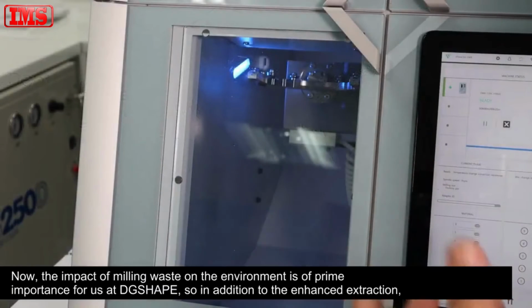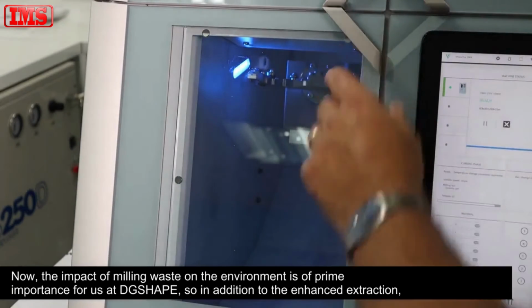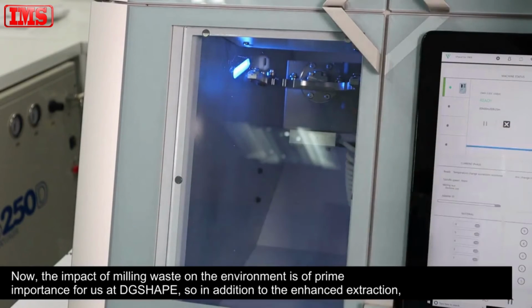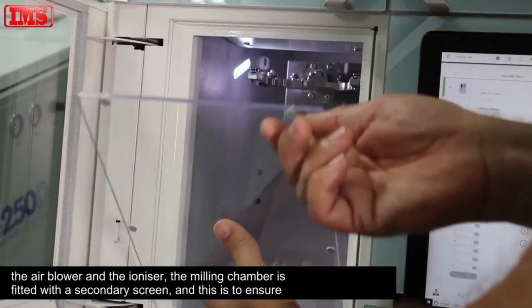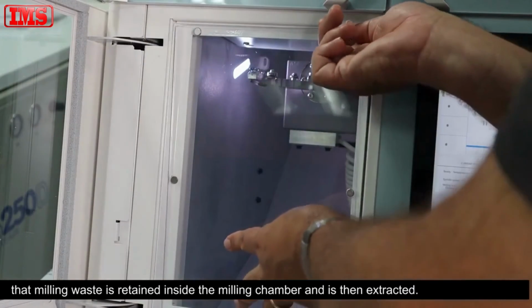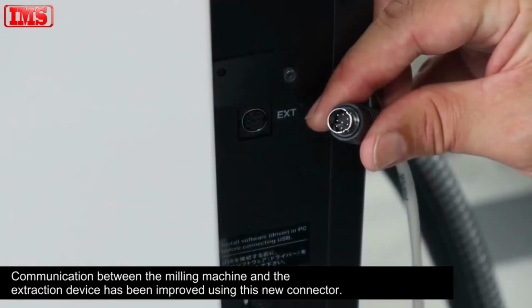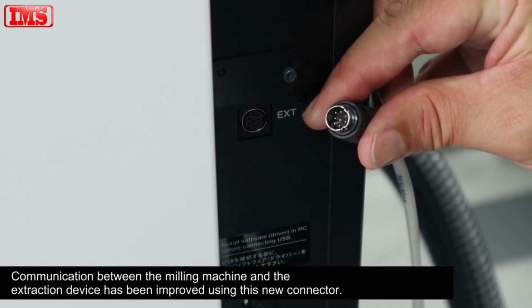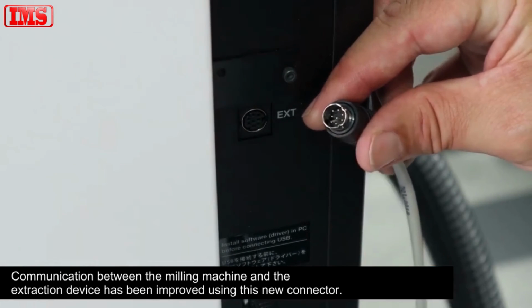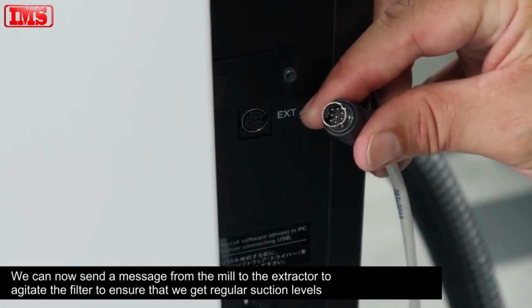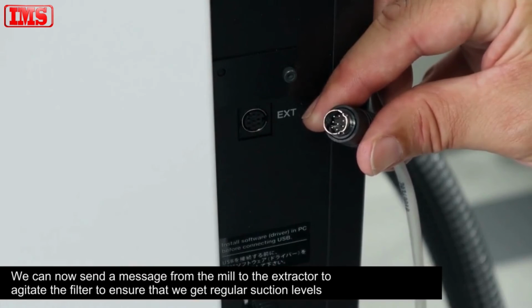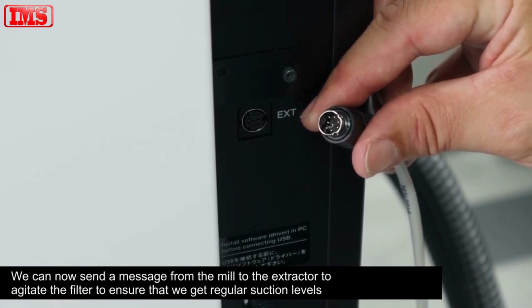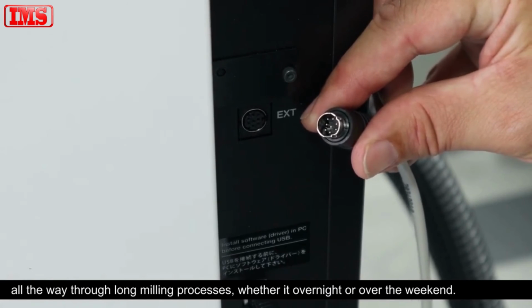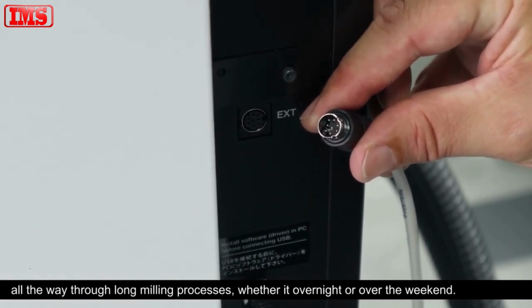Now, the impact of milling waste on the environment is of prime importance to us at DGSHAPE. So in addition to the enhanced extraction, the air blower and the ionizer, the milling chamber is fitted with a secondary screen. And this is to ensure that milling waste is retained inside the milling chamber and then extracted. Communication between the milling machine and the extraction device has been improved using this new connector. We can now send a message from the mill to the extractor to agitate the filter to ensure that we get regular suction levels all the way through long milling processes, whether it is overnight or over the weekend.